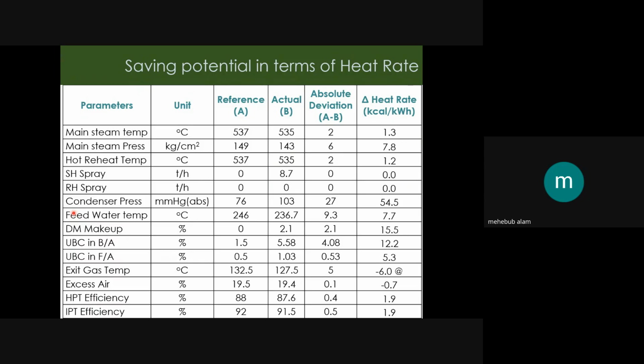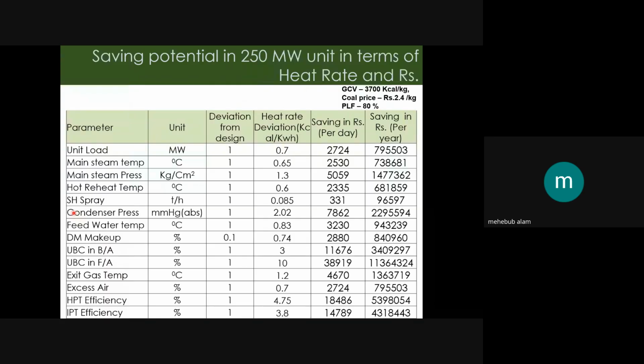From this, we can get an idea of how the different parameters have an impact. Now, coming to the same thing, for deviation from the design value, what will be the impact in monetary value? If there is a variation of load of 1 megawatt, then the heat rate deviation will be 0.7 kcal per kilowatt hour, and that will result in a saving of 2,700 rupees per day. Here we have considered the gross calorific value of the coal as 3,700 kcal per kilogram, and plant load factor PLF is considered at 80%.